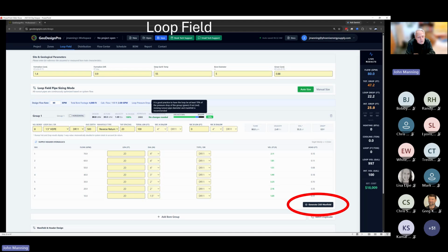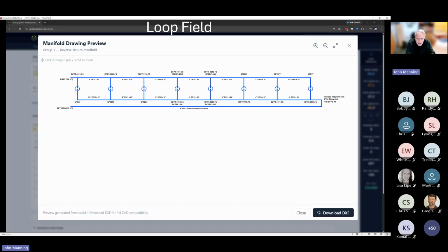However, if you're happy with the design details here, each segment of the reverse return manifold is being automatically calculated to determine the proper diameter. And you can override any of these. You can change the length between bores. Sometimes they may only be a foot apart because the bores are on opposite sides of the reverse return manifold.